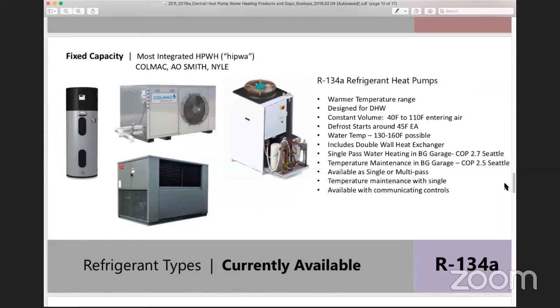The next type of refrigerant is a 134A cycle. These are specifically set up for water heating. They can make up to 160 and 180. These typically will have a double wall heat exchanger. And 134A can handle about 40 to 110 entering air, unless you've got a really good defrost cycle, then you can take the 40 down into the 20s or teens. We've noticed capacity hits of about 50% at 45-degree entering, so it's pretty significant there. And so we typically put these devices in parking garages, which stay above 50 in the winter months. We've got designs now that are achieving about 2.6 COP in Seattle year-round, including recirc.